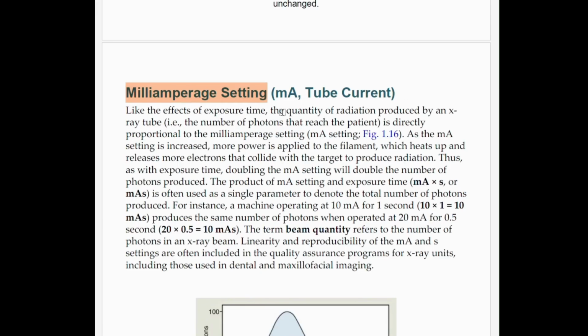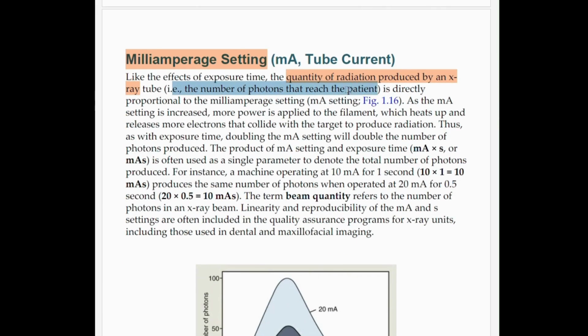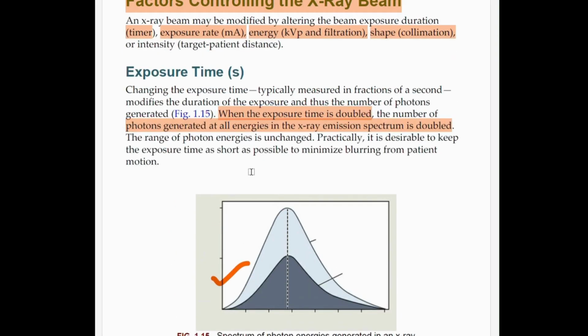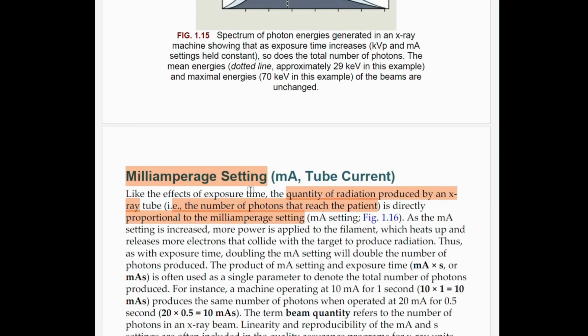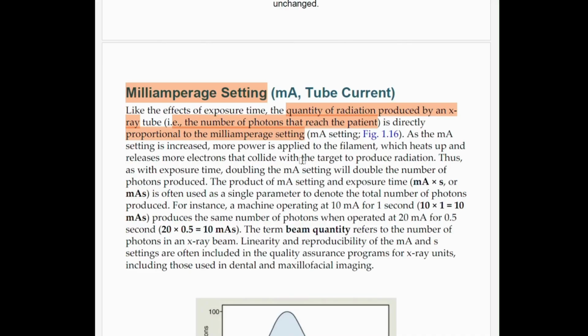Like the effects of exposure time, the milliampere current will tell you the quantity of the radiation produced by an X-ray tube. That is, the number of photons that reach the patient is directly proportional to the milliampere setting. Over here, in exposure time, the important point you need to write is that when the exposure time is doubled, the number of photons generated at all energies in the X-ray emission spectrum is doubled. The milliampere setting tells us about the quantity of the radiation, that is the number of photons that reach the patient. As the milliampere setting is increased, more power is applied to the filament, which heats up and releases more electrons that collide with the target to produce the radiation. Thus, as with the exposure time, doubling the milliampere setting will double the number of photons.